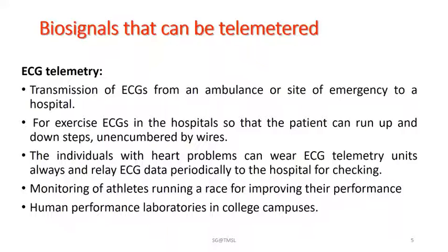Now this transmitter is very small in size. The wire antenna is incorporated in the belt, or it is hung loosely. The clothing has an opening to allow the lead wires from the electrodes to come through to the transmitter. The power for that transmitter comes from a battery, usually a mercury cell, with a useful life of nearly 30 hours.